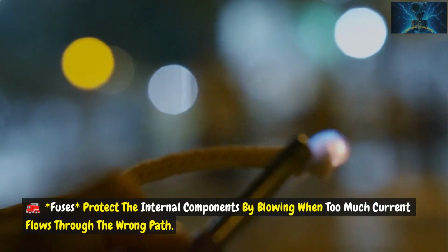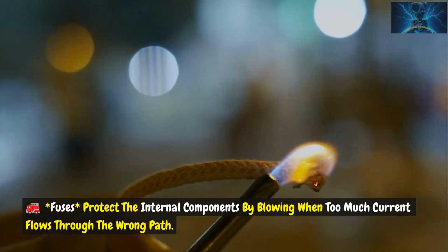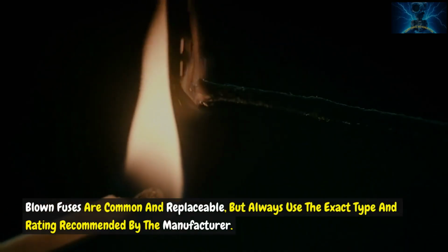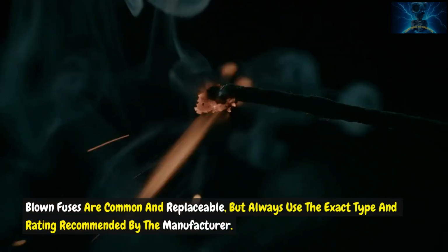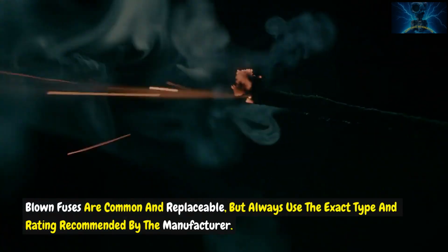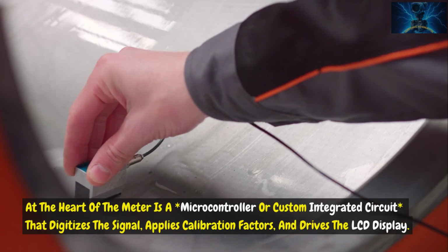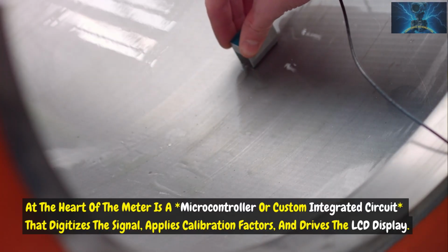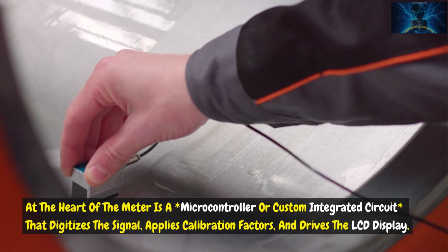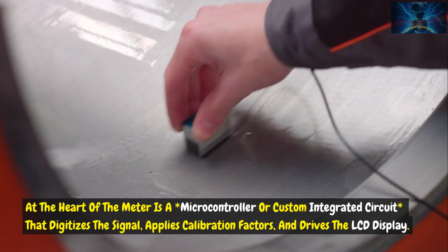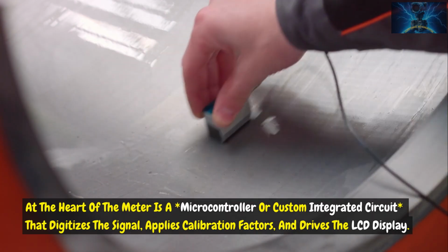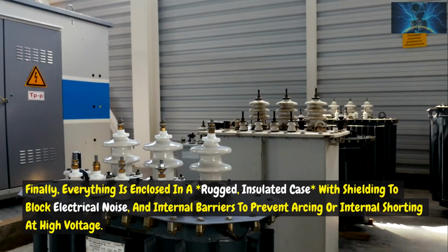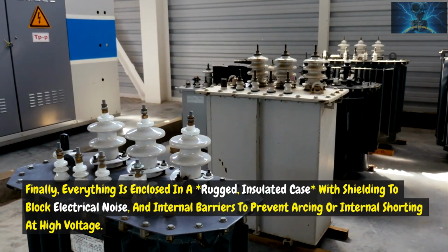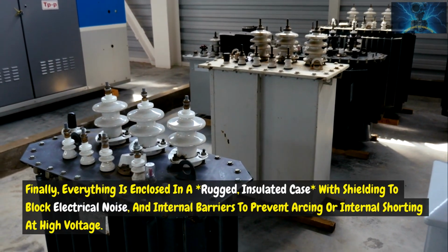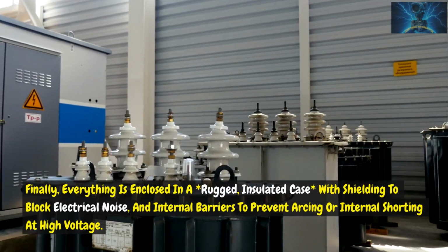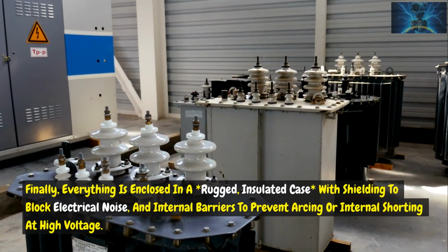Fuses protect the internal components by blowing when too much current flows through the wrong path. Blown fuses are common and replaceable, but always use the exact type and rating recommended by the manufacturer. At the heart of the meter is a microcontroller or custom integrated circuit that digitizes the signal, applies calibration factors, and drives the LCD display. Finally, everything is enclosed in a rugged, insulated case with shielding to block electrical noise and internal barriers to prevent arcing or internal shorting at high voltage.